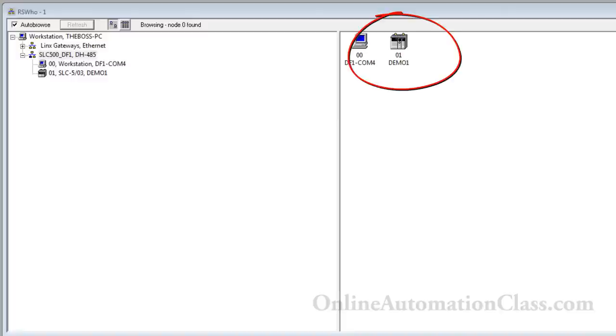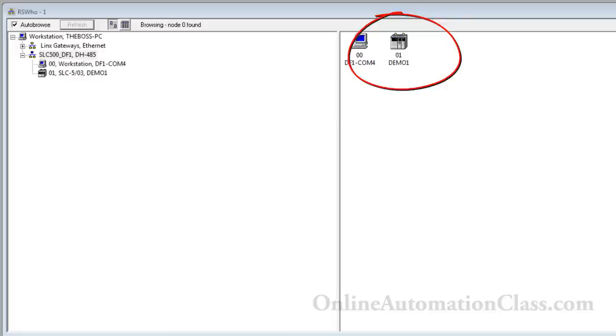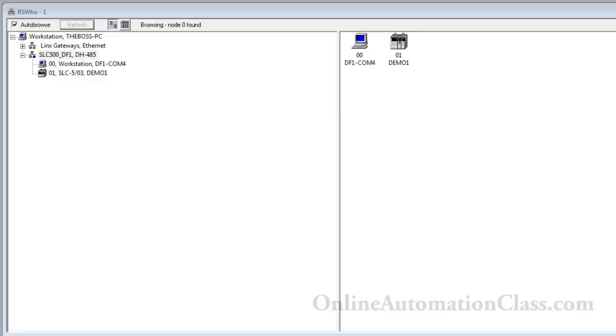Make sure that the SLC500 PLC icon in the device list does not have an X on top of it, because that indicates a communication problem. In this case, there is no X mark on the SLC500 PLC icon in the device list. A DF1 communication link to the SLC500 PLC is now established. The RSLogix 500 Pro program can now interface with the RSLinx program to communicate with the SLC500 PLC.